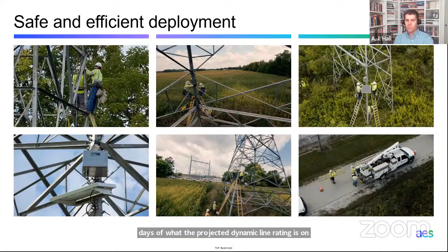And finally, they use a LiDAR sensor—you can see that in the bottom left-hand corner toward the top of the picture. There's a little LiDAR camera that looks up at the 3-phase conductors in the span above it, using that LiDAR position along with a model of the span to calculate wind blowout, conductor sag, and pick out the solar radiation on the line. These data inputs feed into a computational fluid dynamics model fed with third-party weather data to produce a dynamic line rating: an hourly rating, plus a forecast of 240 hours, or 10 days, of the projected dynamic line rating, so that grid operators can use that information to operate the system. Next slide, please.